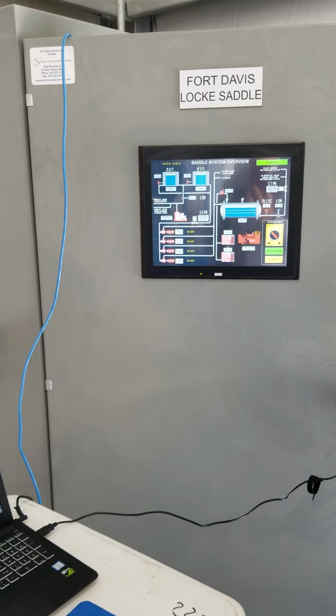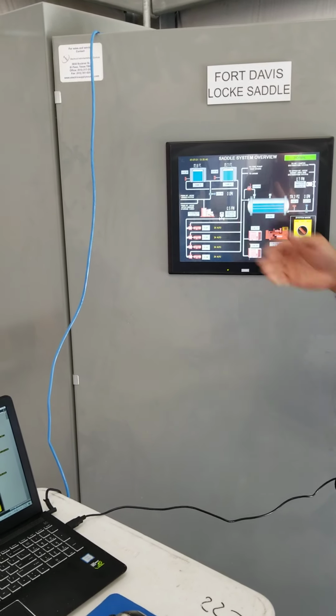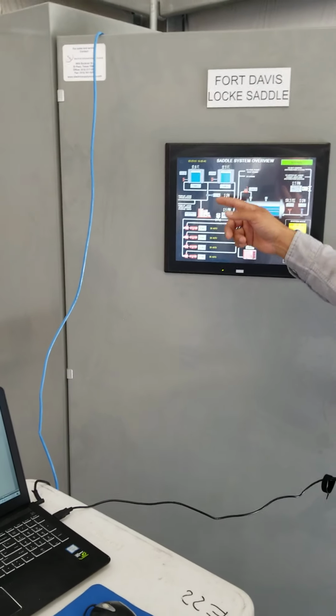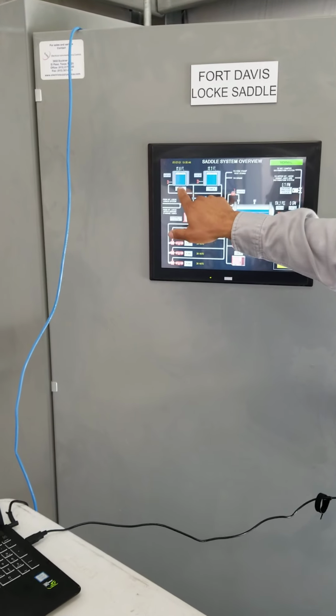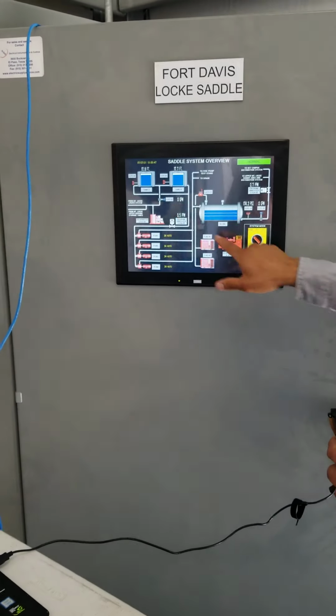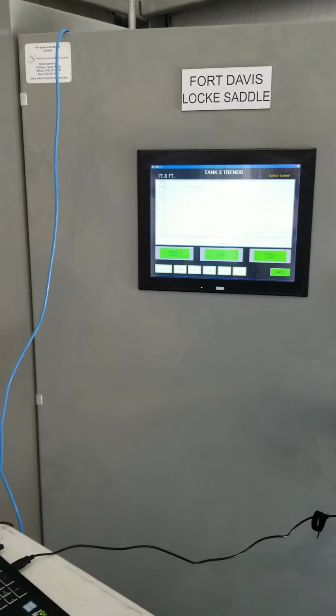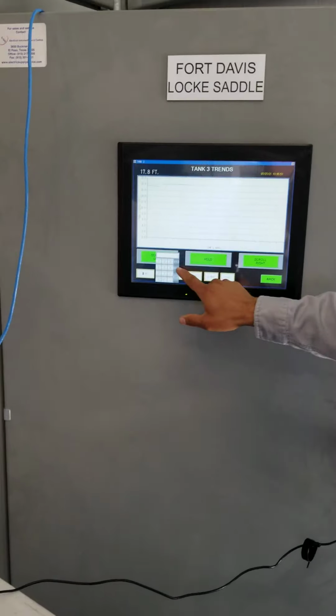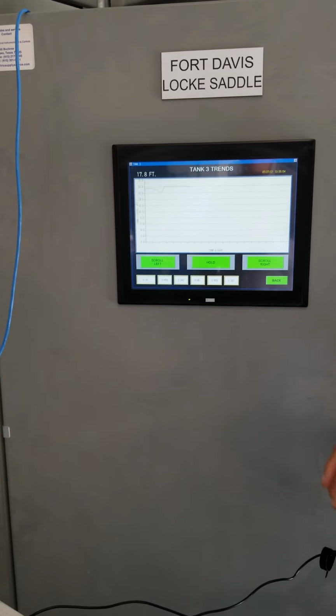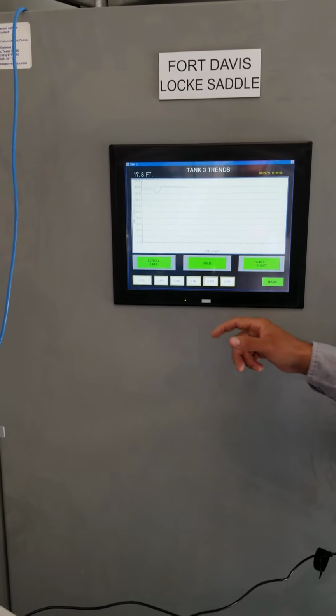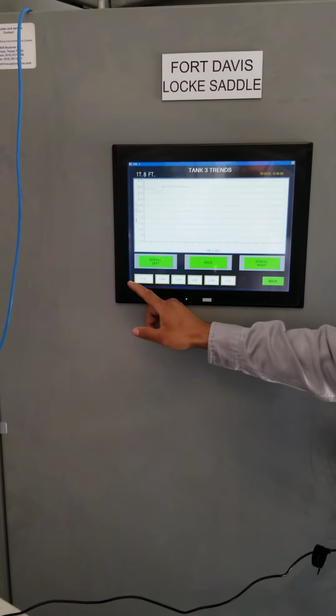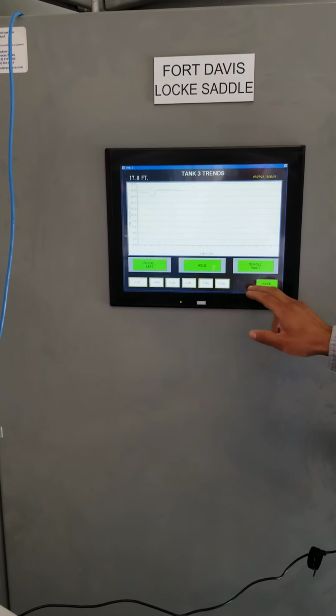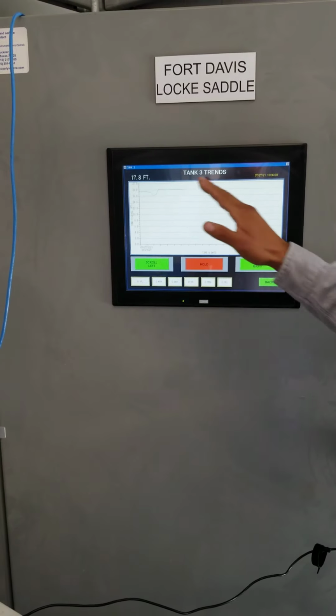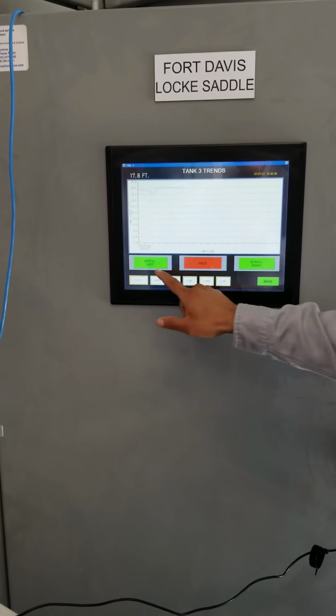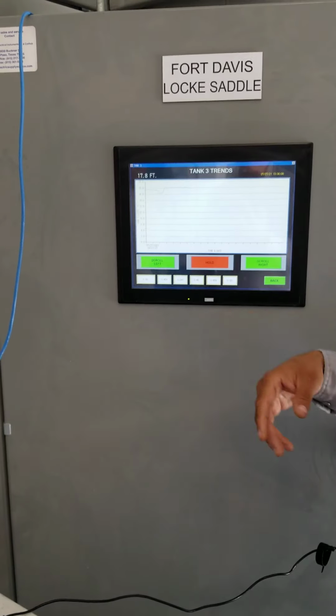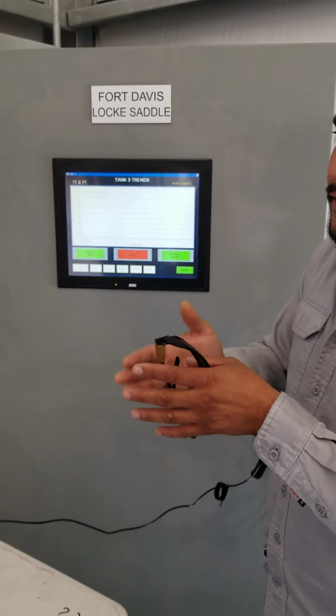On every 4 to 20 signal, like a level, analyzers, flows, they do have trending. So you'll press the tag, and then it'll show trends, and then we'll put here these little squares right here. If you want to go to a particular year, month, day, hour, minute, seconds, up to the seconds, you just put whatever you want to look for. You press it in there, and then you press the hold button, and it'll take you there. If you don't want to mess with this, you just scroll back and forth. Right now, we just downloaded the program, so give it some time to store some data.